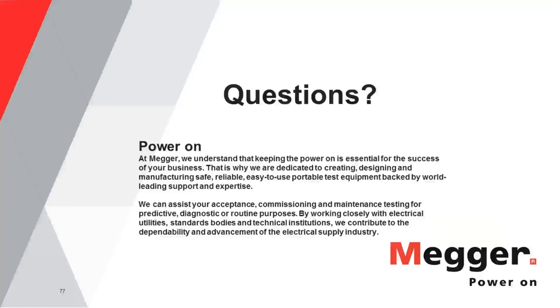For low voltage cables, do both ends of the cable need to be disconnected before measurements, or can we leave one end connected to an open breaker? Connected but not energized. Okay, so the thing to consider here is that whatever is connected to the other end will also be tested when you are testing the insulation. So if you are interested only in the cable part, you should disconnect the other end.